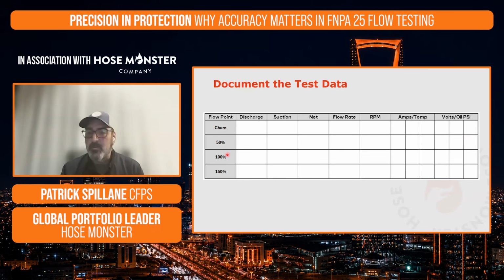Now, a standard annual flow test per NFPA is going to be our churn, 100% and 150% of our rated capacity of that fire pump. However, I do know that there are a lot of companies out there that also like to do a 50% flow test. So for the placard example that we saw, that 1,500 gallon per minute pump, we would set our flow rate to 750 gallons a minute and take our readings there. All of this is going to go into what we call the curve of the fire pump, all this data that we're collecting.